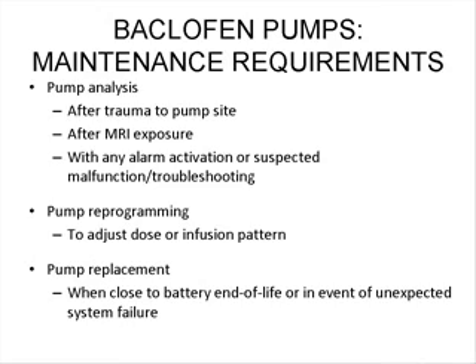With any activation of the alarm system, so these pumps have an alarm system that will tell you when there's a problem, or it perceives that there's a problem based on what's programmed into the pump information. The important thing to know is that this doesn't always sense when there's a problem. It tells you that the pump's low on fluid or empty based on what the programmer tells it should have at any one time. So it doesn't sense anything. So if you hear any alarm activation or you suspect there's a malfunction of the pump system, then we would want to see you to be able to interrogate the pump.